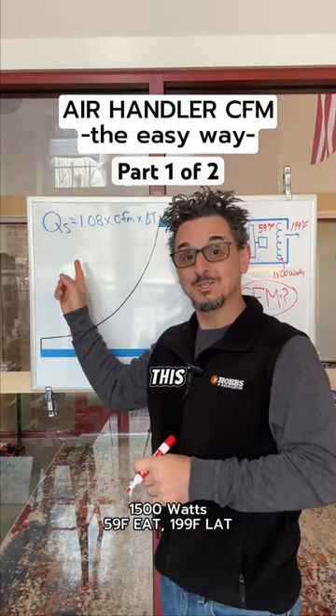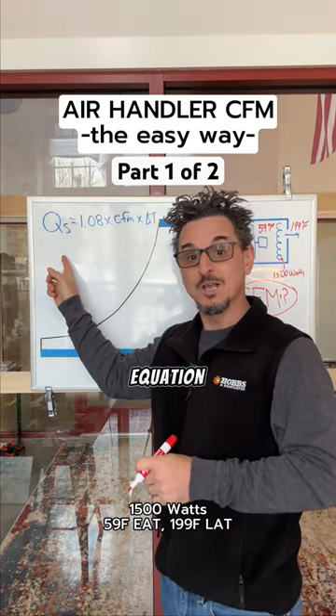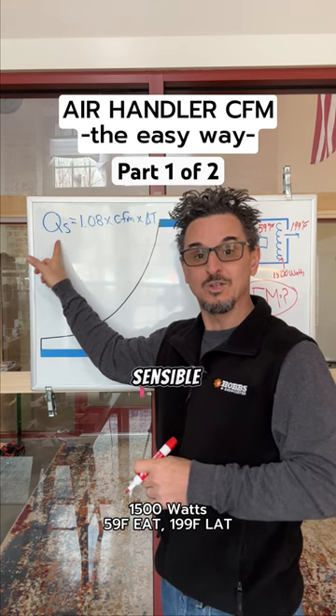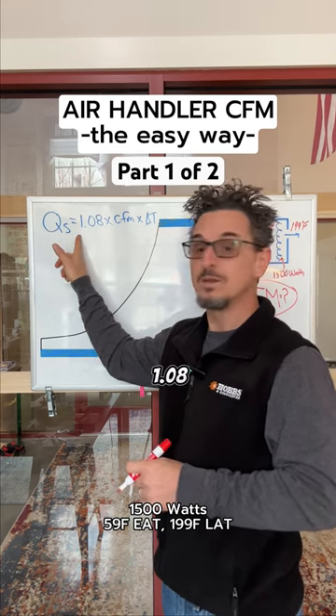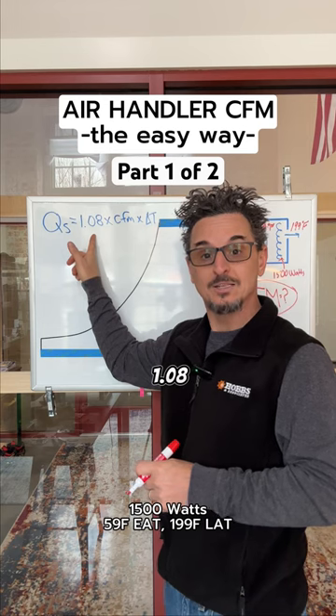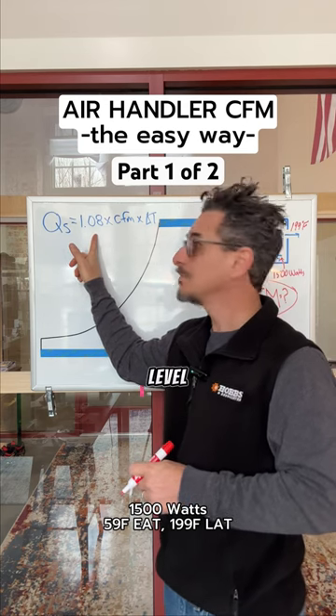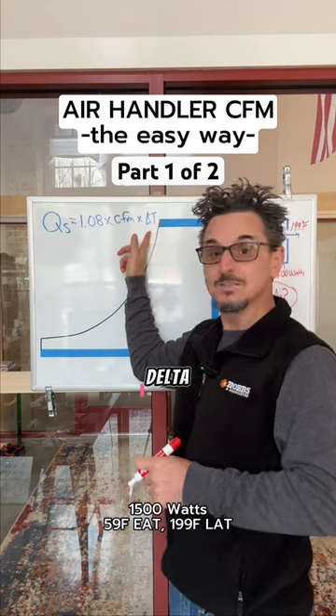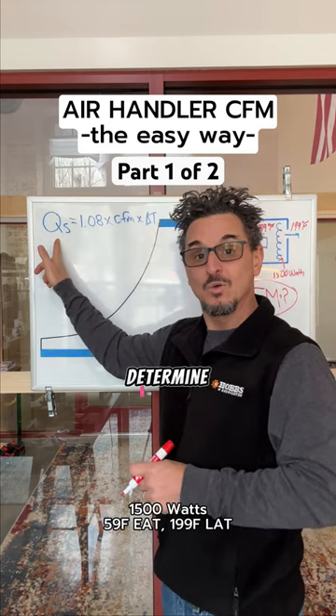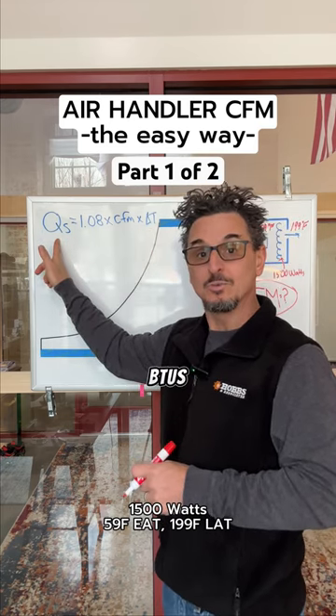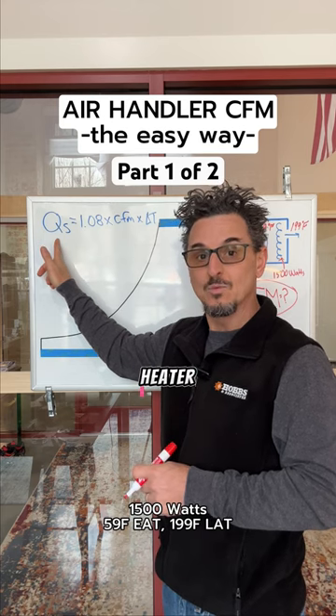To answer this question, we're going to use the sensible heat equation: QS is the sensible heat, or BTUs per hour, which equals 1.08 at standard air conditions at sea level, times CFM, times Delta T. We're going to solve for CFM and determine what the BTUs per hour are from the electric heater wattage.